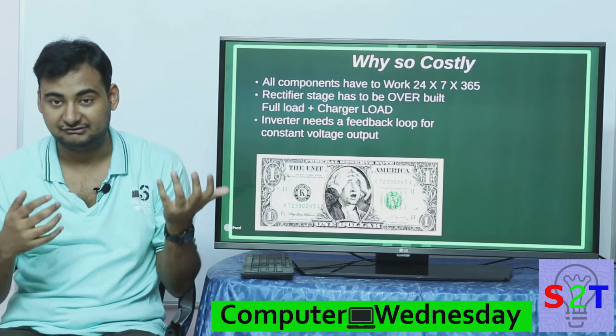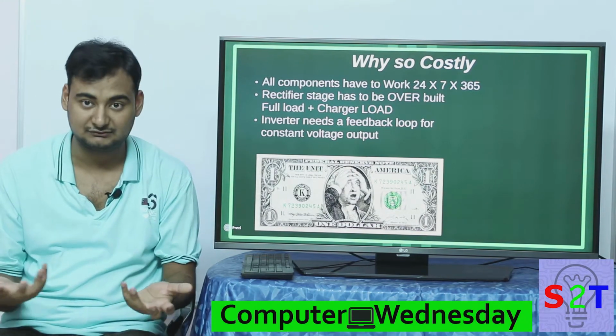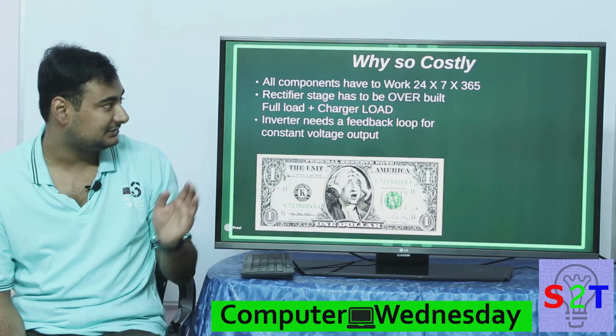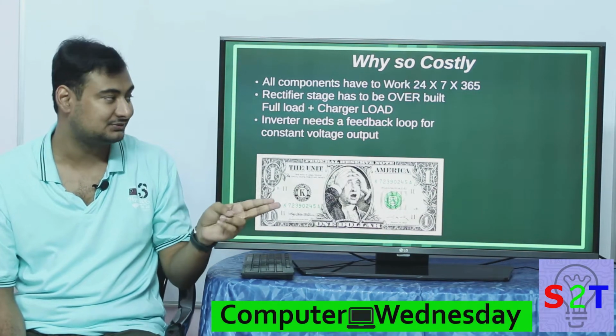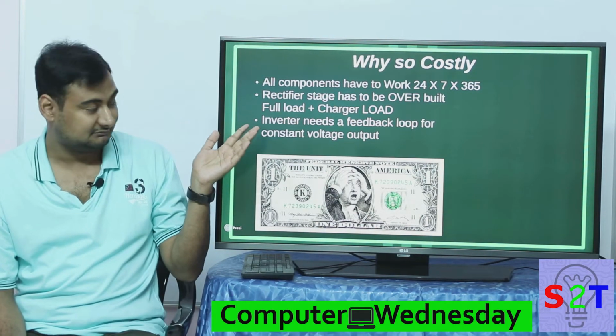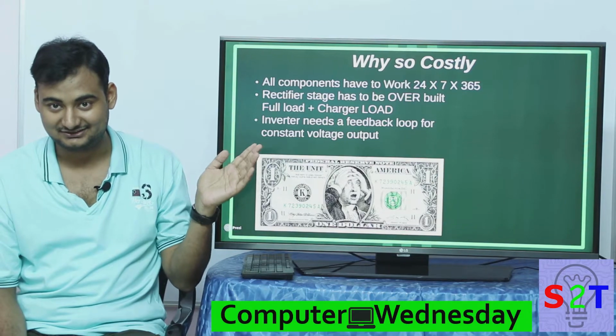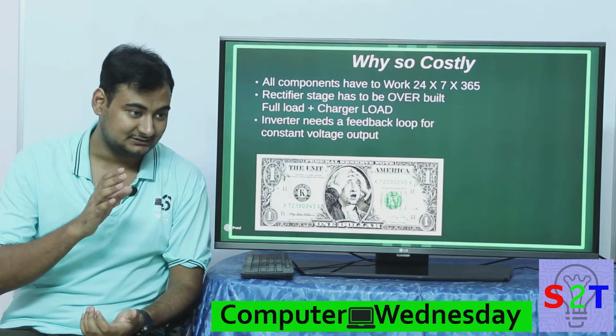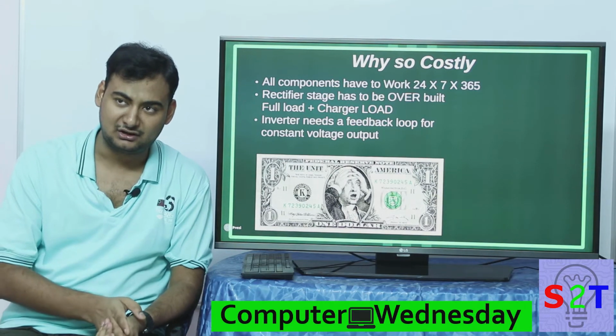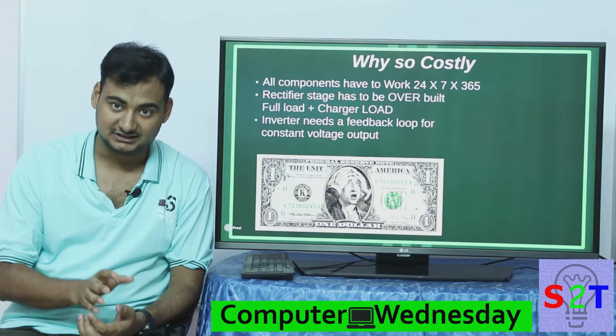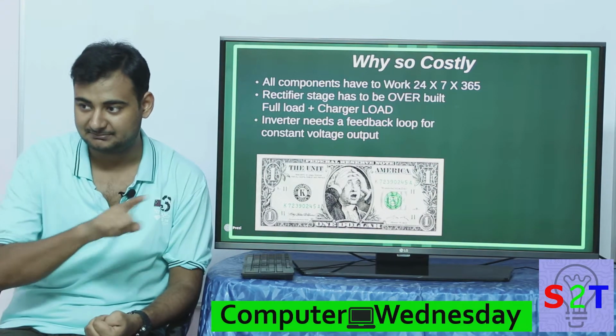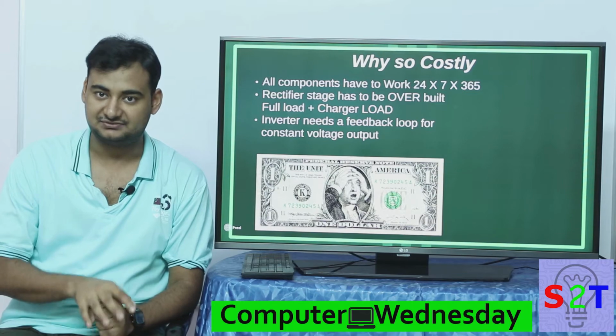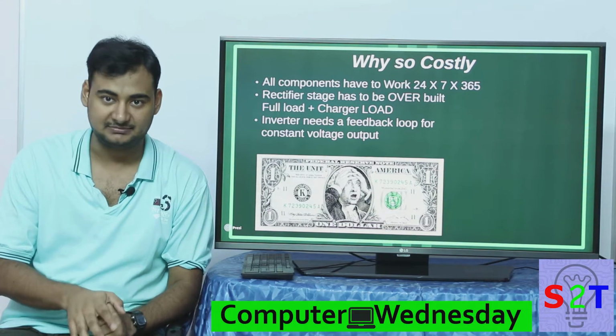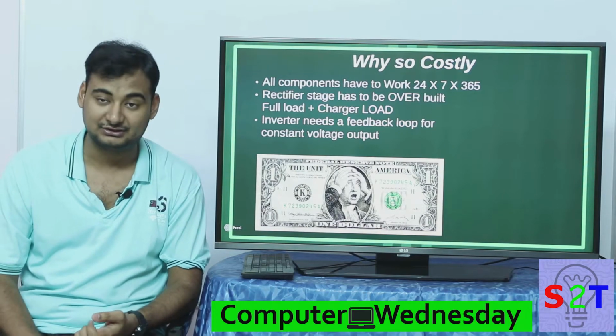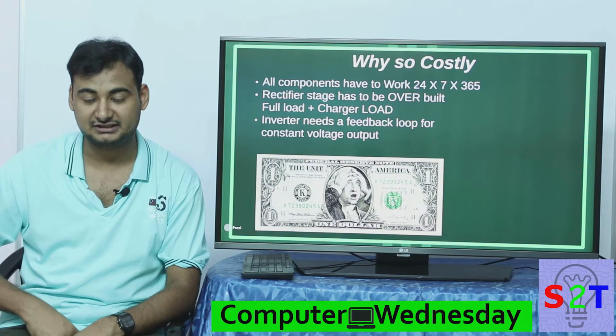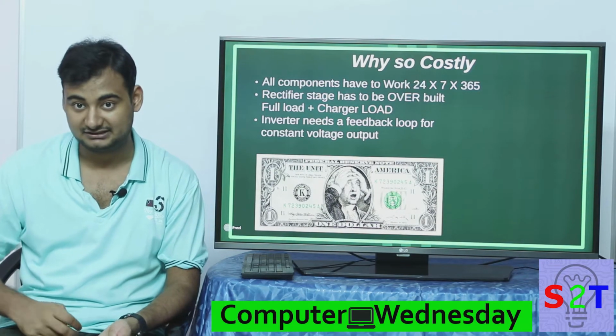Now you have to understand, if this is so good, why the heck is it so expensive? Of course, the need would be so high that it should be cheap. But you have to understand, these are designed to run 24/7, 365 basically, and they should also run as long as their warranty is there, so suffice to say 3 to 5 years. The reason is it never ever turns off. There is no off. Your very old style UPS simply bypassed to the mains. So the rectifier stage only worked as long as it needed to charge the battery. Once the battery is charged, it's cut off. Here it has to work 24/7, as long as any load is connected to the UPS. So that is a very big problem.